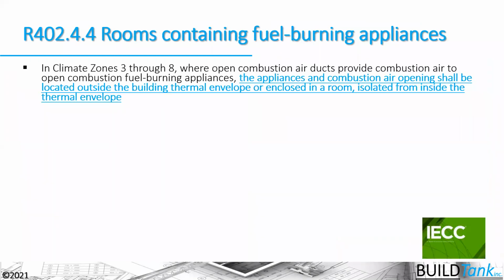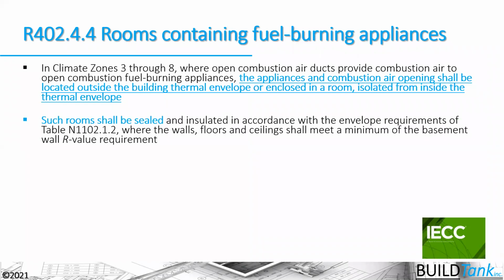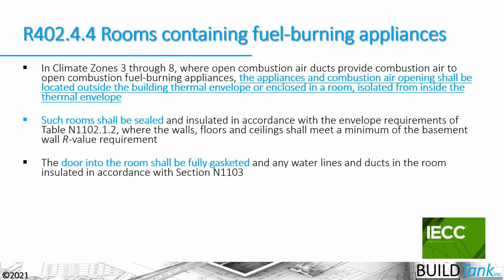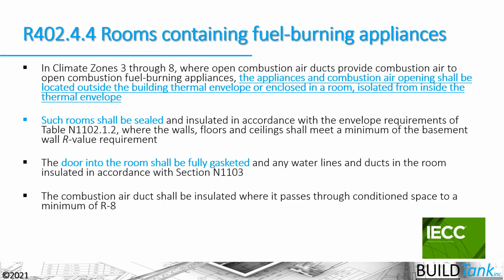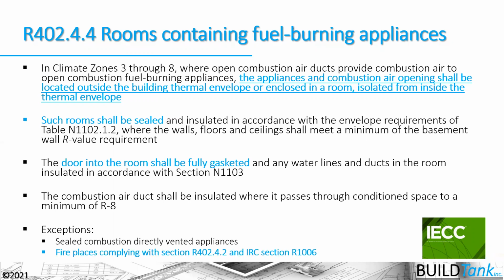Now, for combustion air, the code does say that rooms containing fuel burning appliances that are bringing in combustion air, they're atmospherically vented equipment, that you really are required to build a sealed room that defines the building envelope so that that room is outside the building envelope. It has airtight doors that are fully gasketed. All the penetrations through that building envelope are airtight and sealed there. The door is shut during the blower door test through that. All ducts inside that room are insulated properly. All these things should happen. I would say in general, most jurisdictions are not enforcing this or doing a good job with this. But in essence, if you're not using sealed combustion appliances, you're supposed to have an airtight room that separates the combustion air from the rest of the air inside of that house.